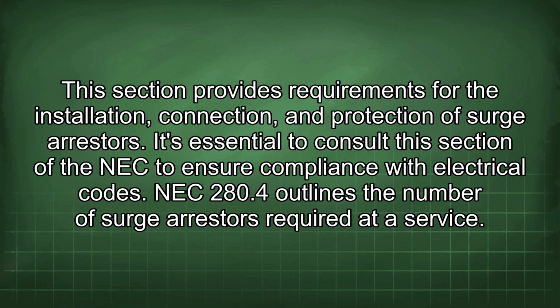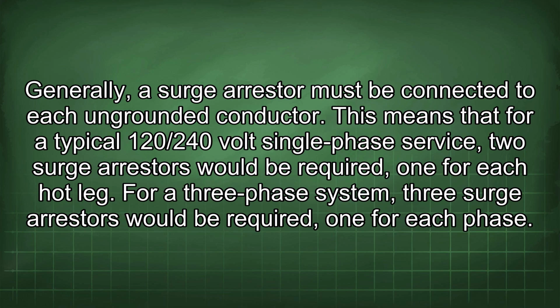NEC 280.4 outlines the number of surge arrestors required at a service. Generally, a surge arrestor must be connected to each ungrounded conductor. This means that for a typical 120/240 volt single-phase service, 2 surge arrestors would be required, 1 for each hot leg. For a 3-phase system, 3 surge arrestors would be required, 1 for each phase.